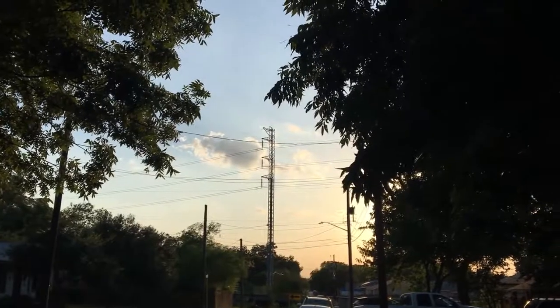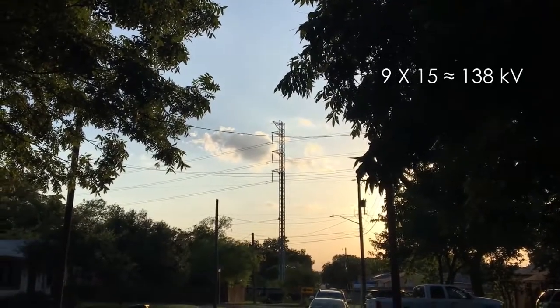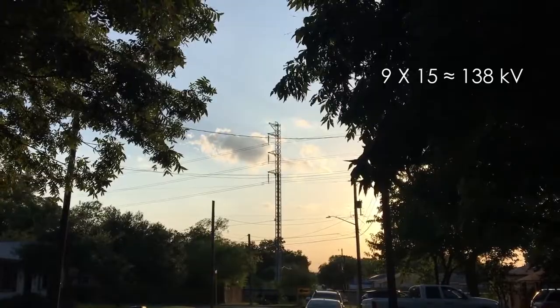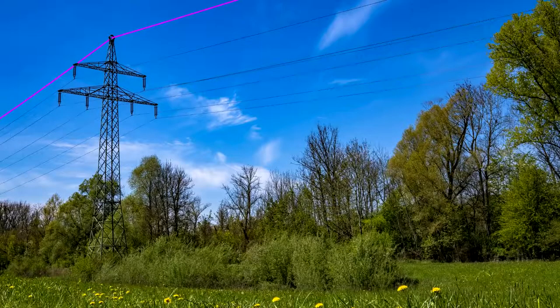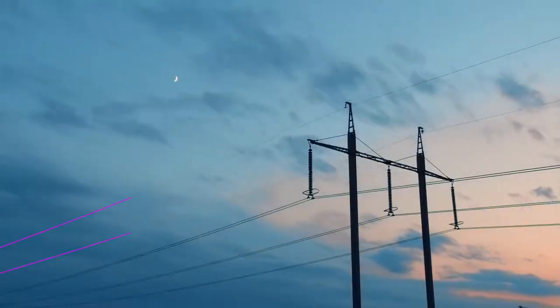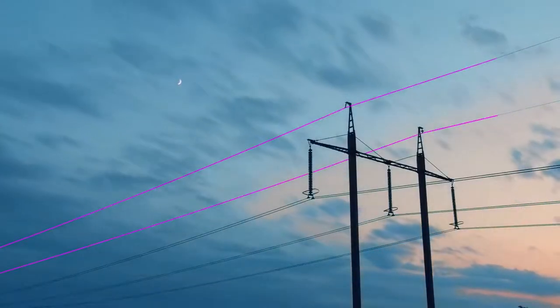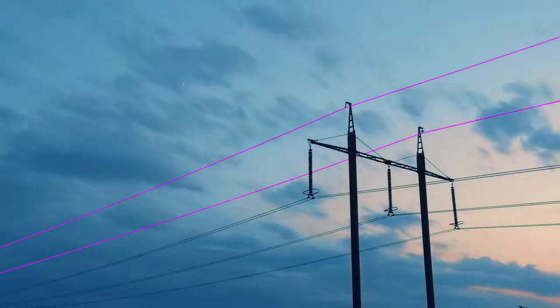For example, this line near my house has 9 discs on each insulator, and I know it's a 138 kilovolt line. You'll also often see smaller conductors running along the top of transmission lines. These static or shield wires aren't carrying any current. They're there to protect the main conductors against lightning strikes.